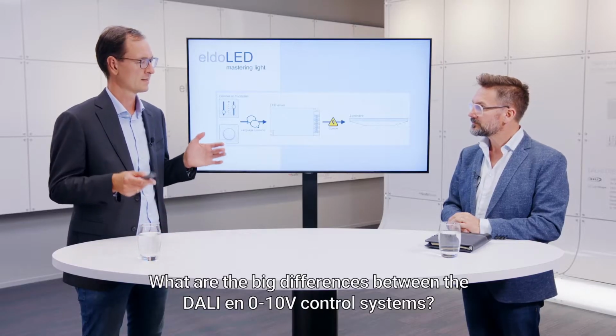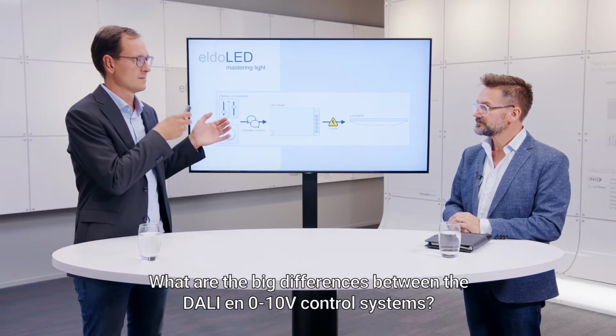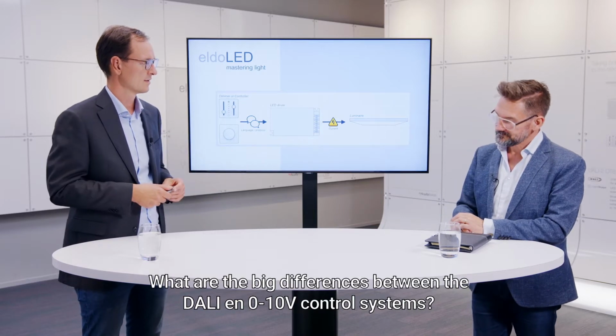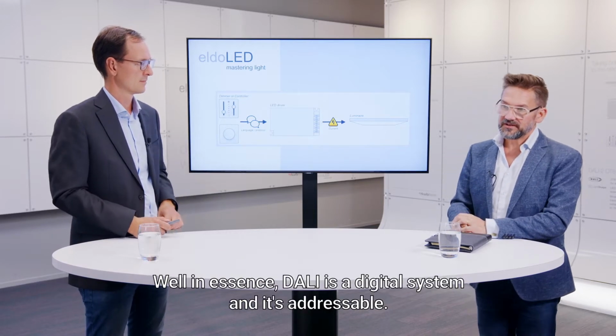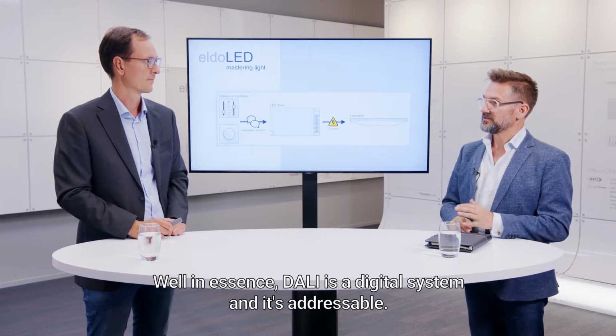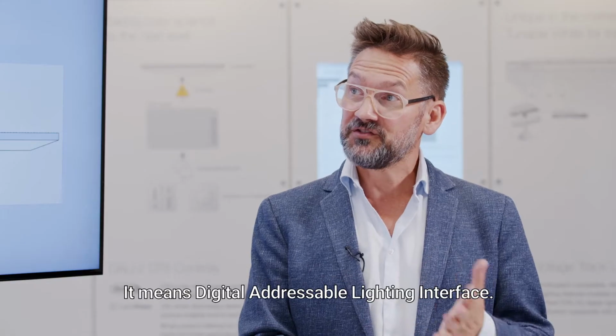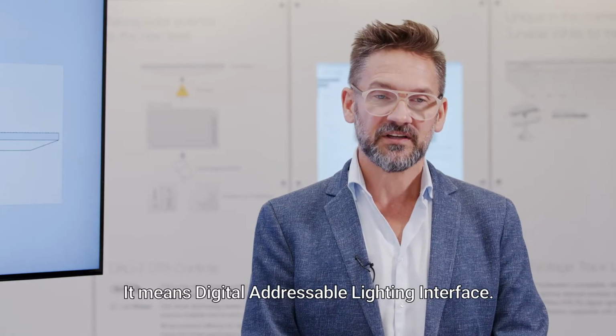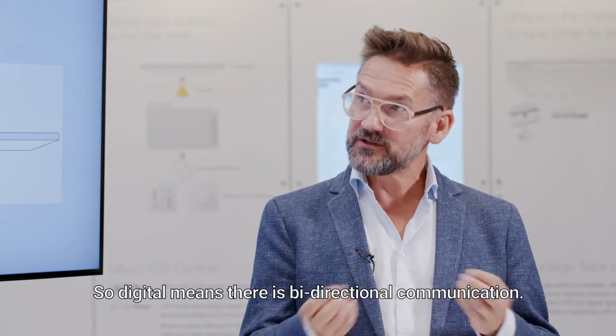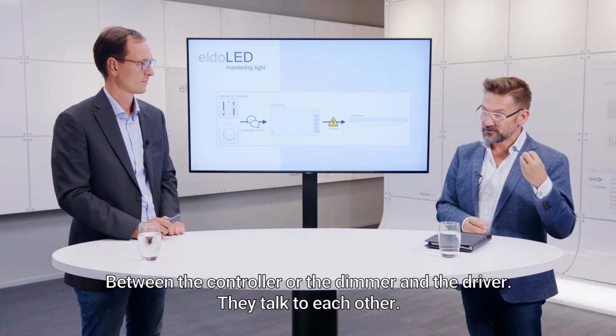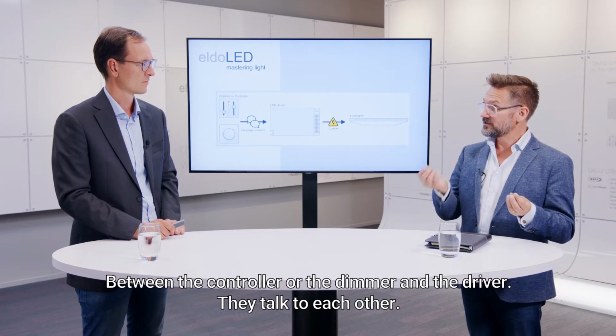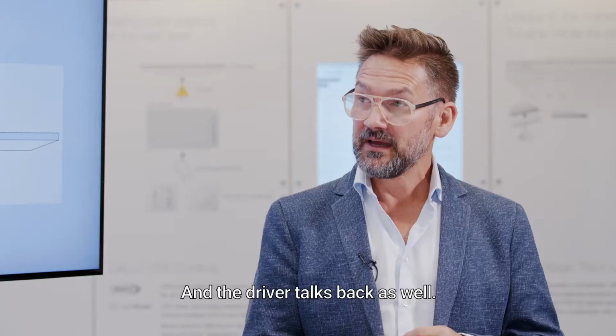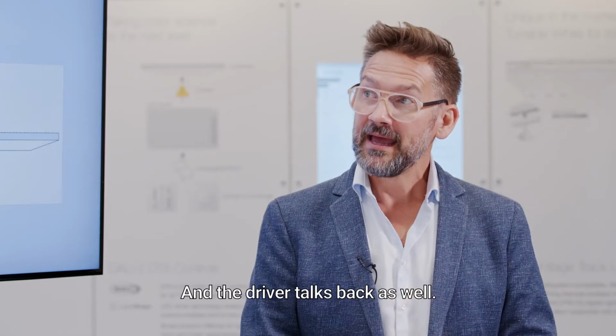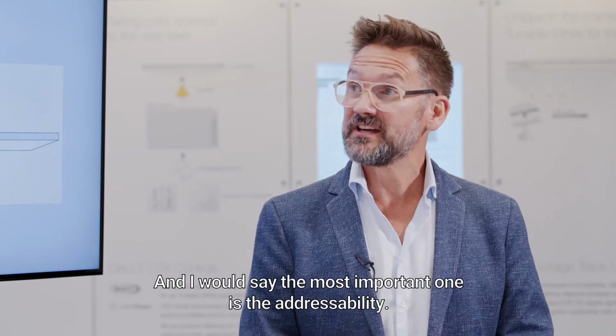So what are the big differences between that DALI and 0 to 10 control system? Well, in essence, DALI is a digital system and it is addressable. It means a digital addressable lighting interface. So it's digital, it means there's bidirectional communication between the controller or the dimmer and the driver as such. They talk to one another and the driver talks back as well. And I would say the most important one is the addressability.